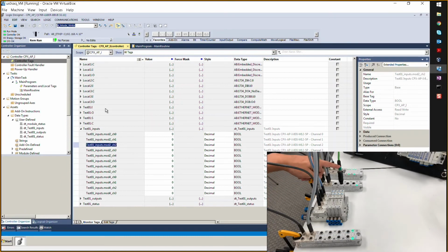Okay, it's running and everything says it's okay. So theoretically, I should be able to push the button again and now see. If you push the button, you now see your button is on module 2. It is on module 2, channel 4. So 0, 1, 2, 3, 4, 5, yeah. Channel 4, and then this should be channel 0, I believe. Yep, channel 0.